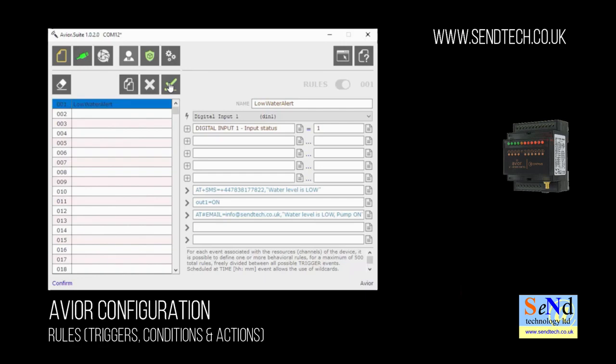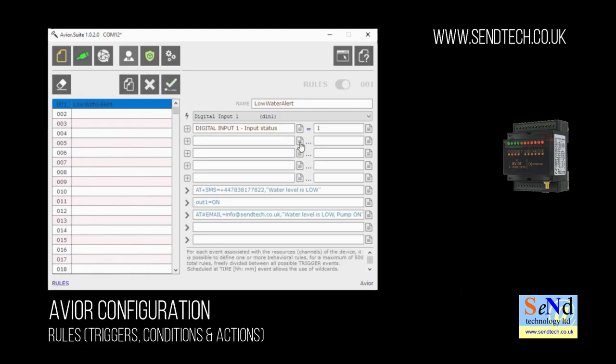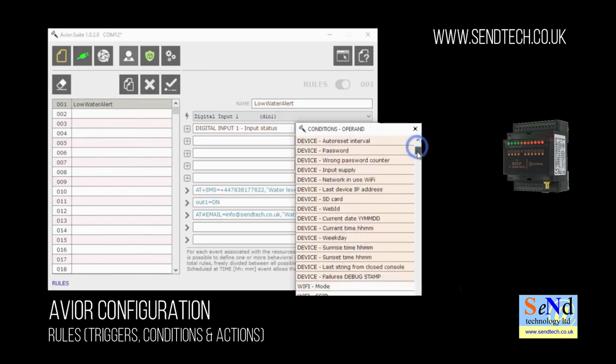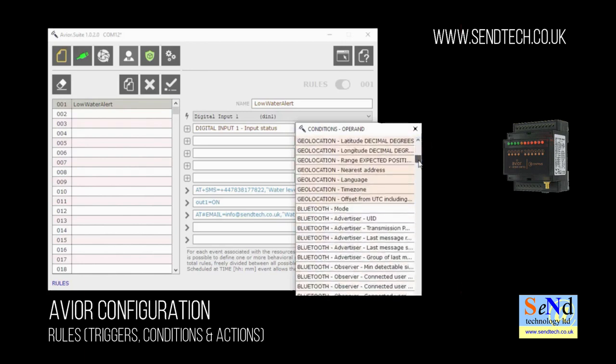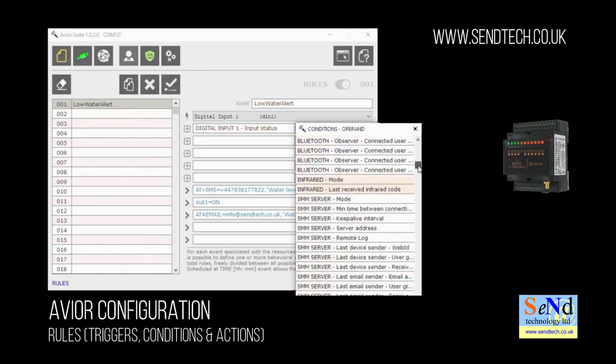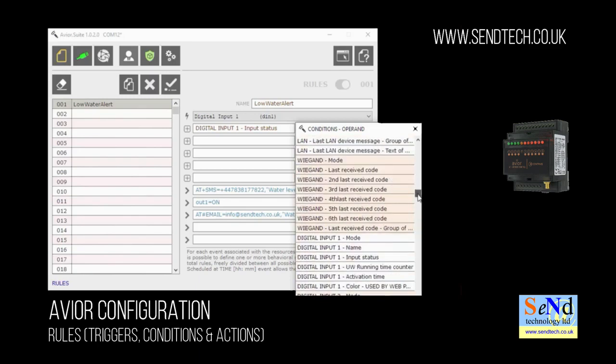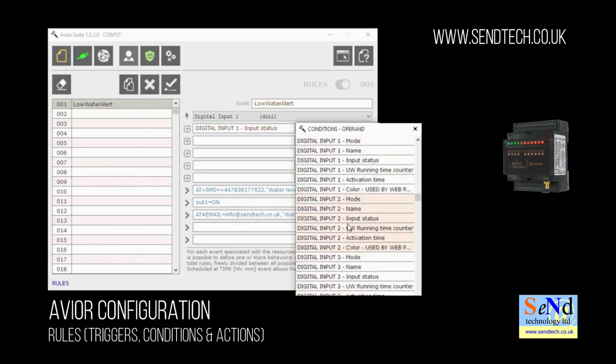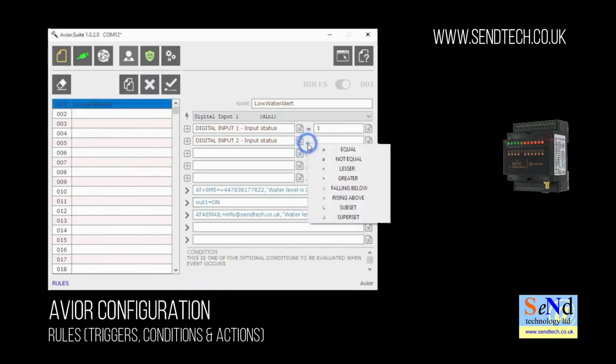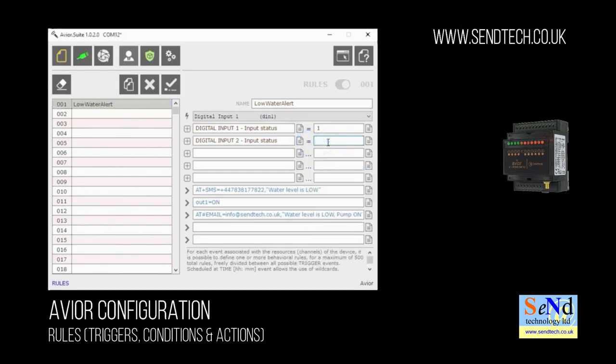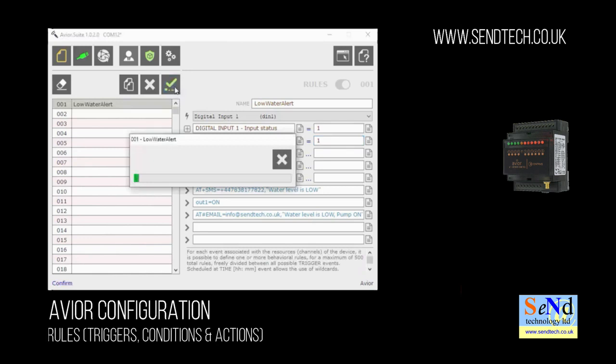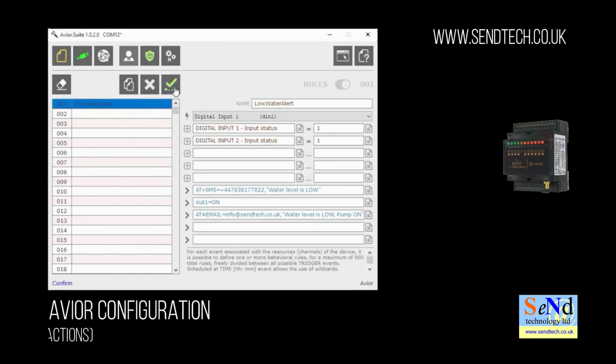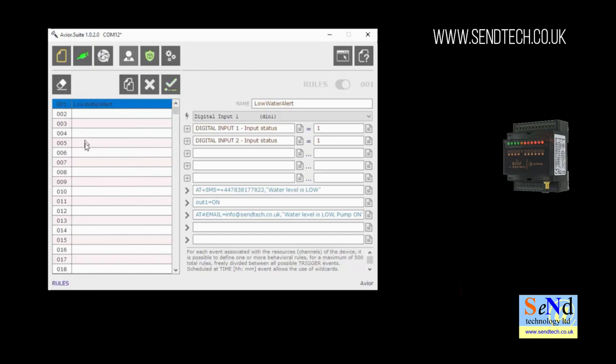So let's add another condition. In this case we'll make sure digital input 2 is on at the same time. So again we'll choose the drop down list, find digital input 2, find the input state again and equal that to 1. So now in this example we're looking for both inputs to be on before we carry out the actions below. As you can see this can be quite a versatile product.